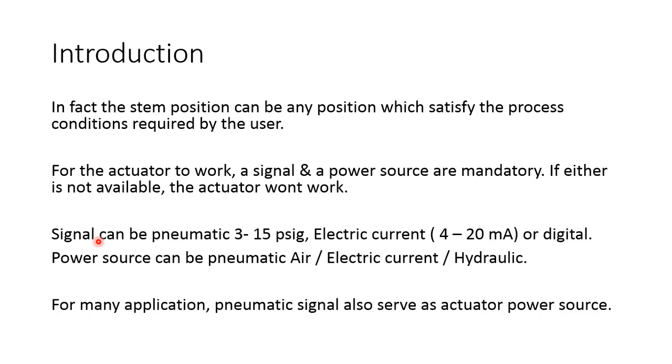So based on that, when 12 milliampere is given, the stem is halfway in the valve. In fact, the stem can be at any position based on what the signal has been given, either from the control room or it can be cascaded from the system itself. There could be a situation where the signal can be pneumatic, that is 3 to 15 psi for a simple pneumatic actuator with a pneumatic positioner, or it can be an electric current, it can be a digital, it can be HART or a Profibus signal, and power source can be pneumatic, air, electric current, or hydraulic.